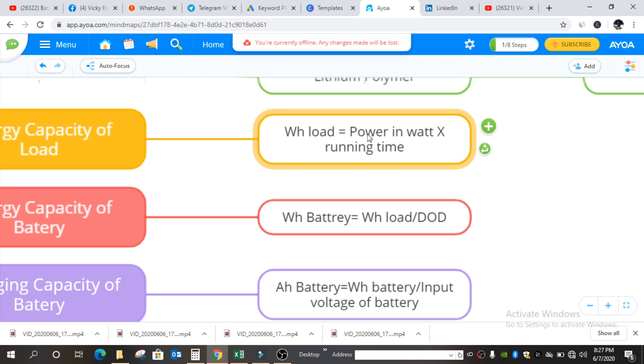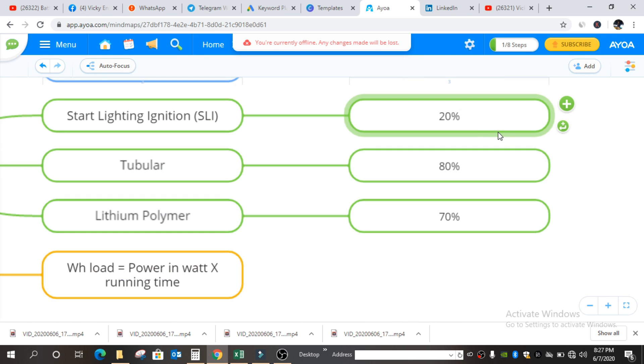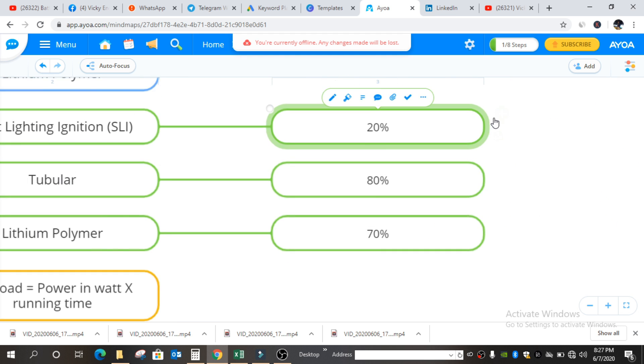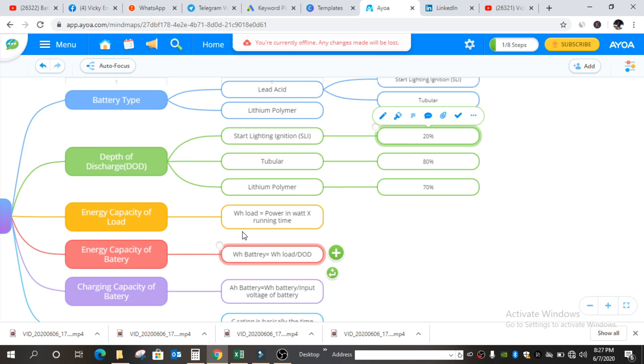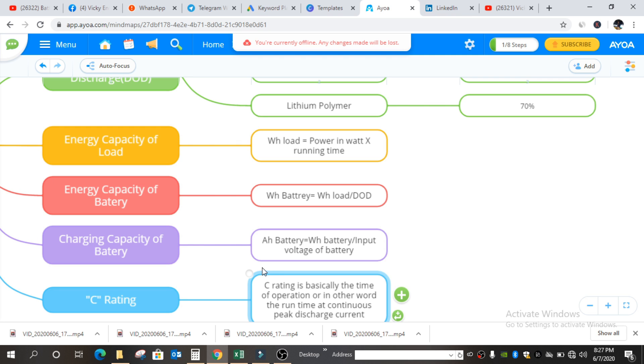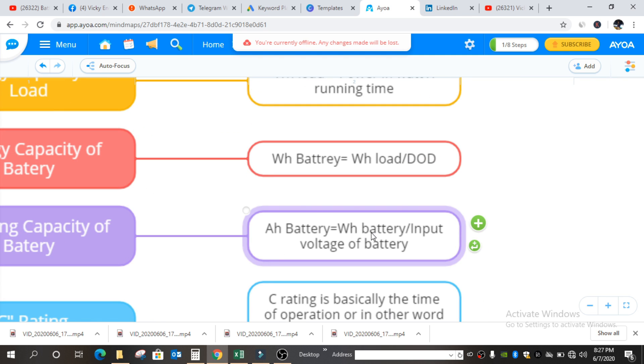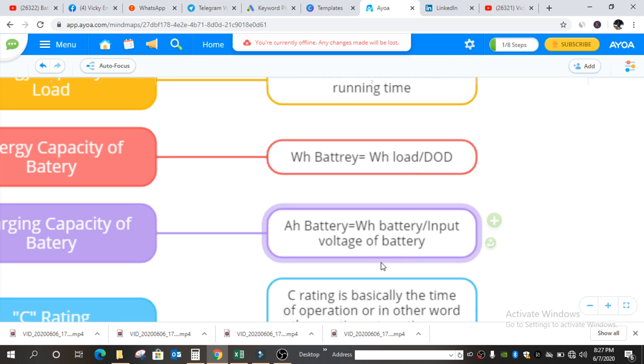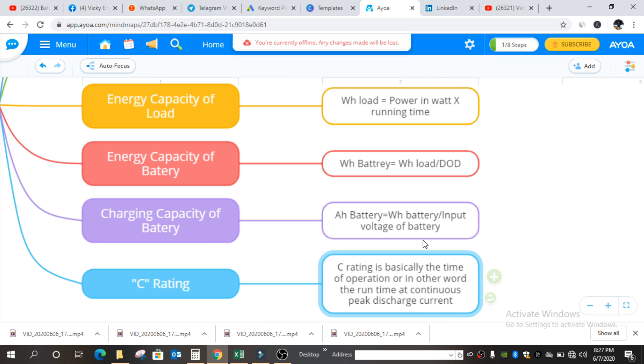WH capacity of load, as we know, is power in watts multiplied by running time. The depth of discharge we get from the battery type: if the battery is tubular it is 80%, if SLI it is 20%. Next is charging capacity of battery, that is the AH capacity. AH of battery equals WH of battery divided by the input voltage of the battery. Normally in India the battery input voltage is 12V.